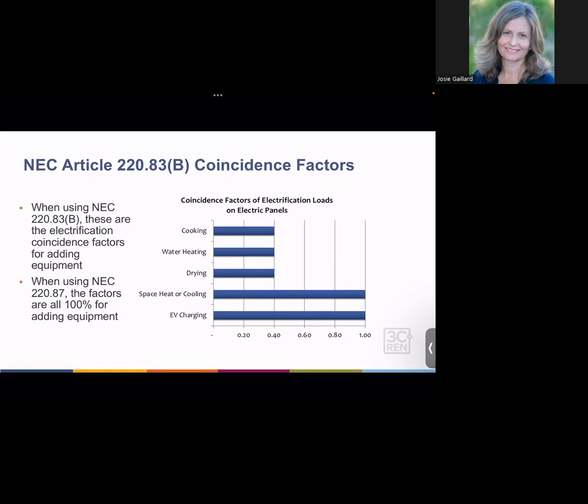Now moving to the other way we can look at doing load calculations for a home, this 220.87 section of the code, there everything gets a 100% coincidence factor. So nothing gets derated, but instead of building everything up from the bottom up using nameplates for the existing loads, instead we're going to use the historical electrical peak for the home across the past year. So instead of looking at all those nameplates on the existing appliances, we're going to use their utility data. And then bring in the new appliances. For those, we still have to look at their nameplates. For the new appliances, we're going to apply a 100% demand factor.